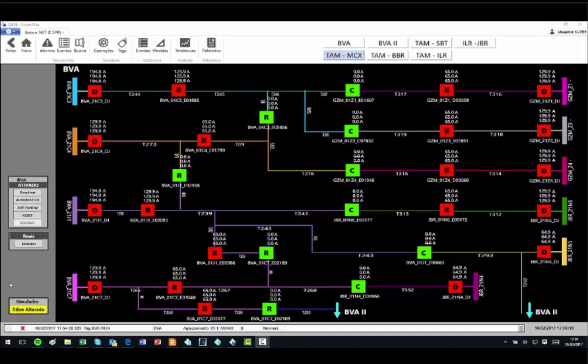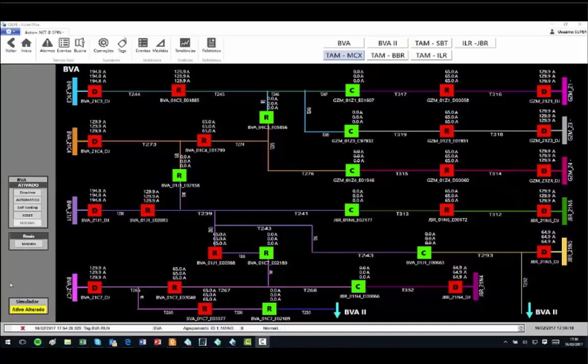In this way, we can simulate faults and switches and loads, and this information will be sent to ADMS FLISR that will run the topological processor, the state estimator, and the contingencies FLISR module, and will suggest maneuvers to isolate the problem and restore the system. In the simulation module, it is possible to study all the possible contingencies.